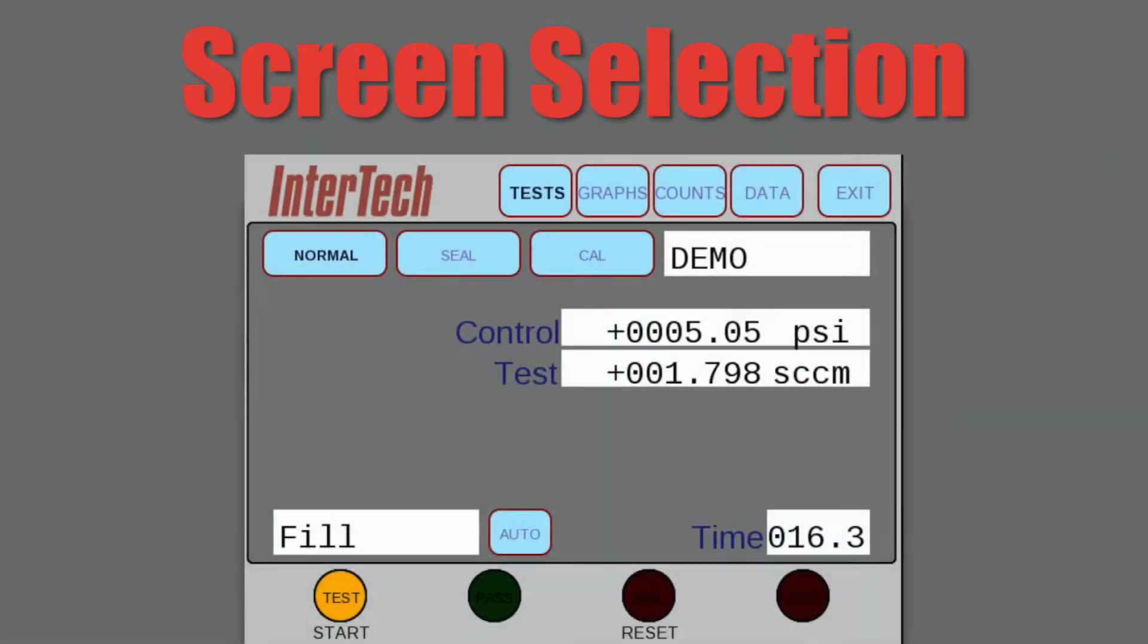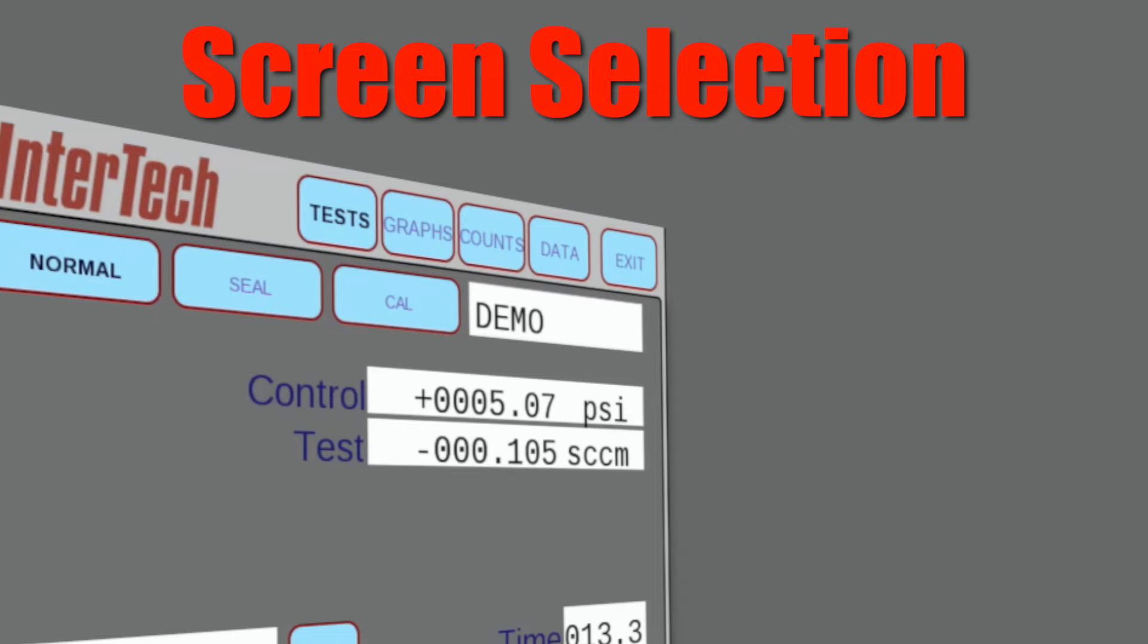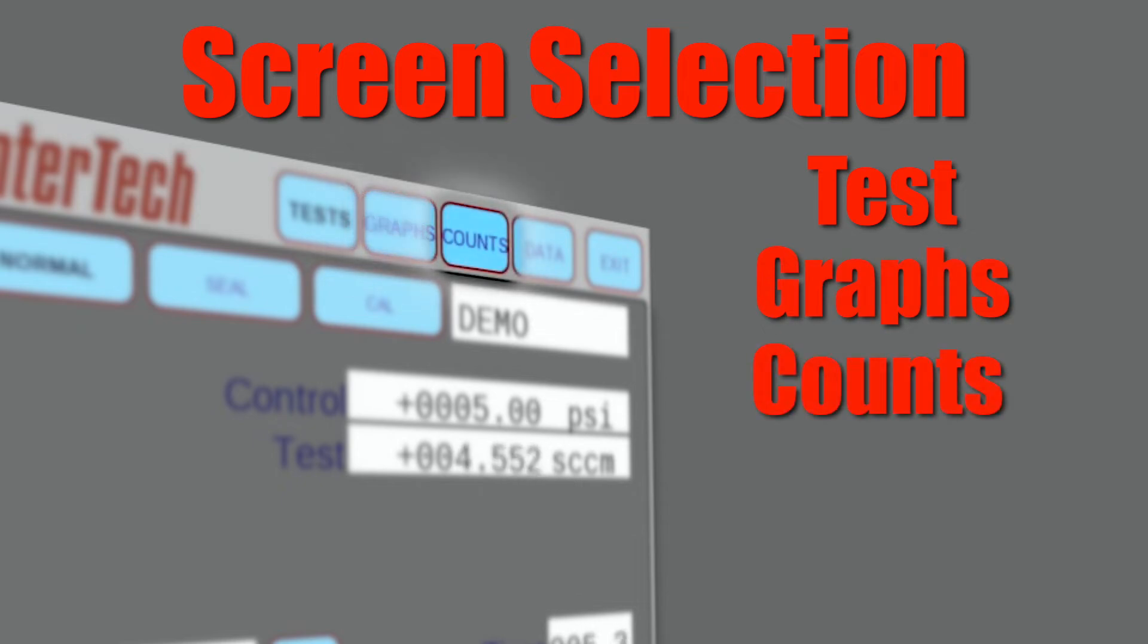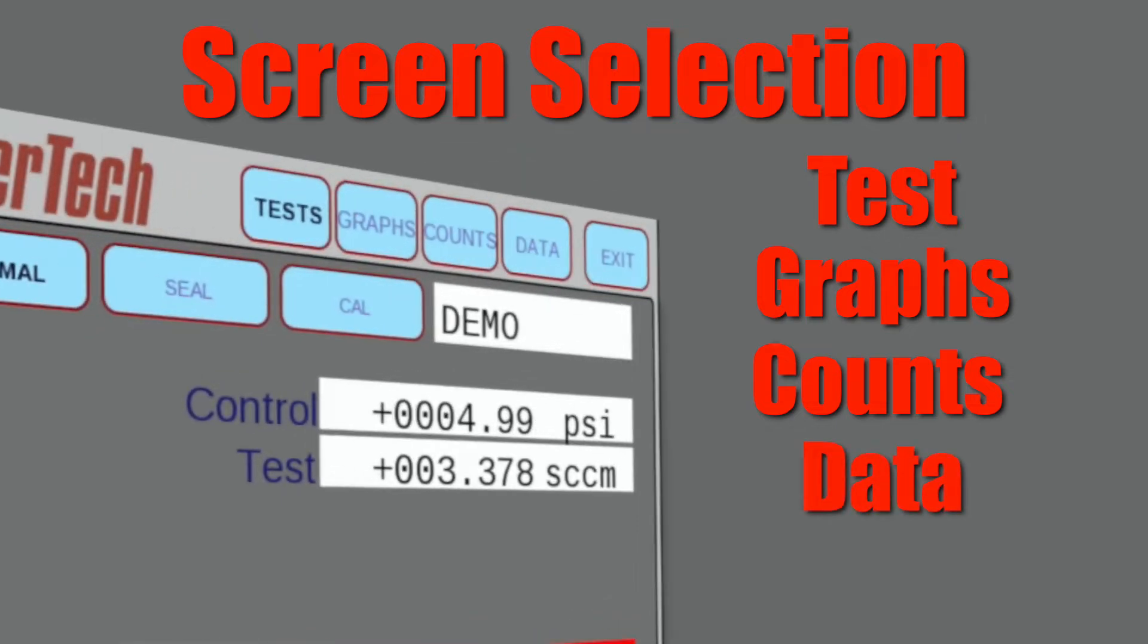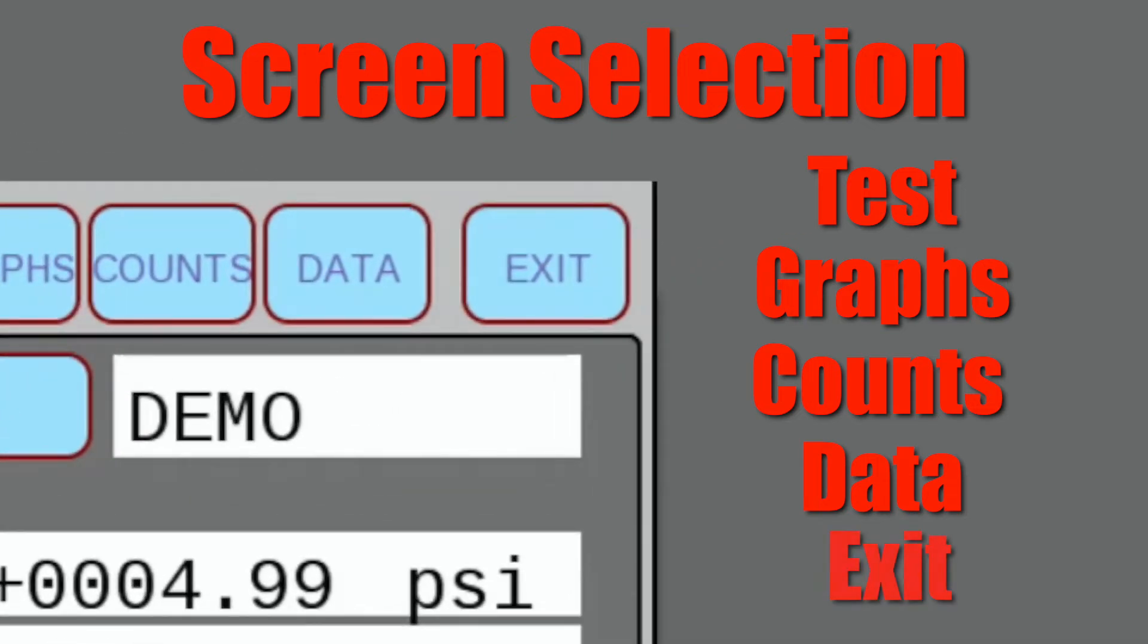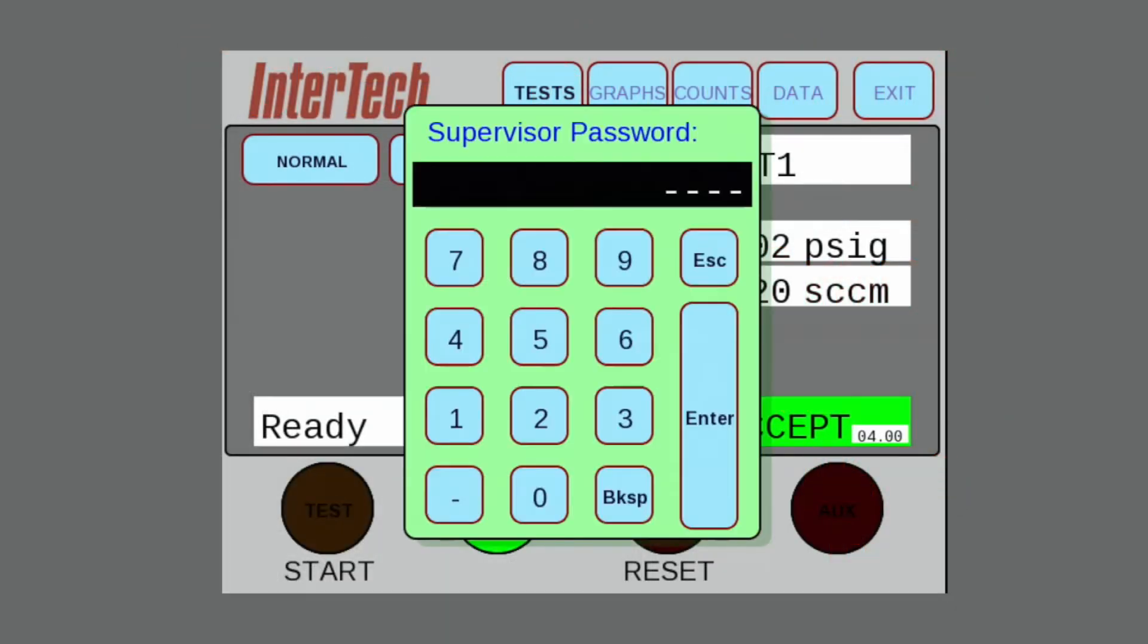User screen selection option buttons are along the top row. Operators can select test the main screen shown, graphs to see the real-time flow curve of the test, counts to view the number of accept and rejects, and the data display showing recorded values for each test. To enter into supervisor functions, the exit button is selected, which transitions to the password-protected supervisor selection screen.